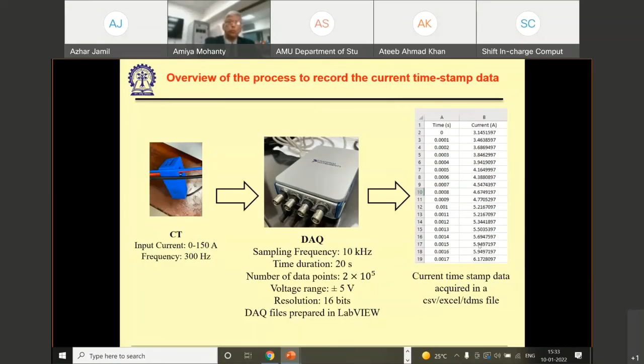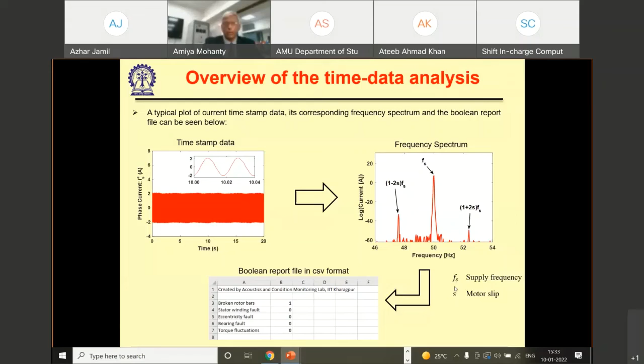From the spectrum - this is done in our lab - we can say whether the motor has a broken rotor bar. It can detect all these 5 conditions: broken rotor bar, stator winding fault, eccentricity fault, bearing fault, and torque fluctuation. So this is what we can do.